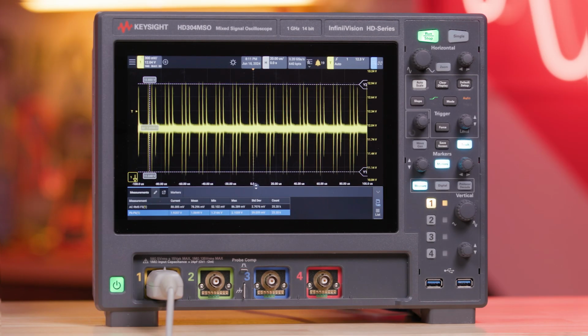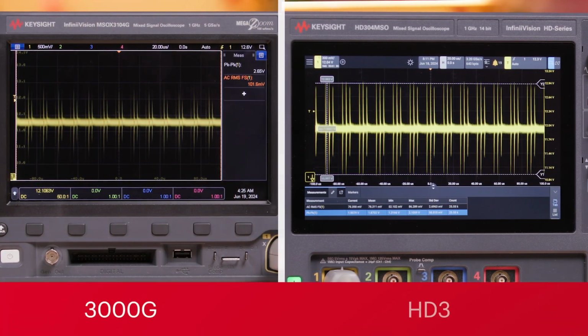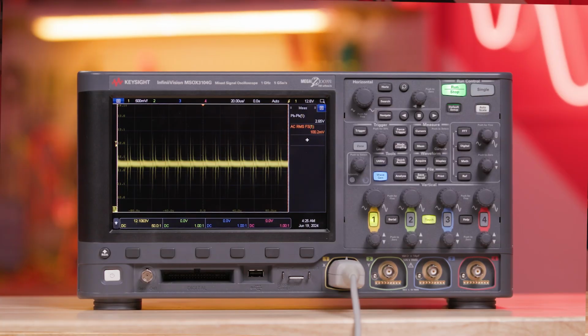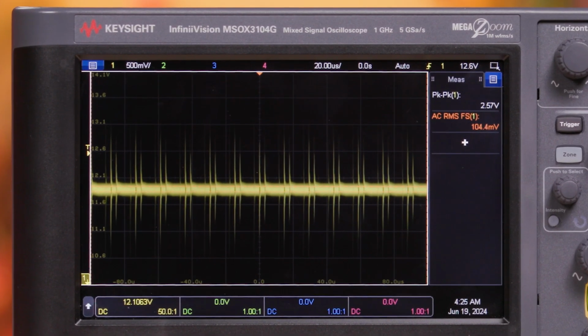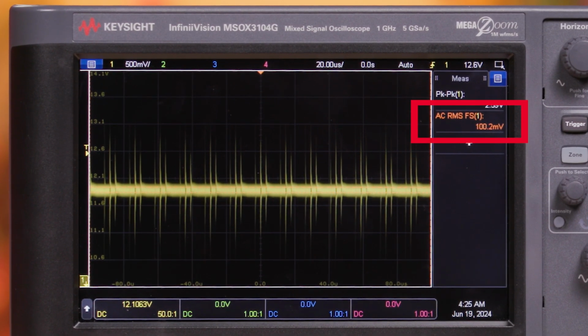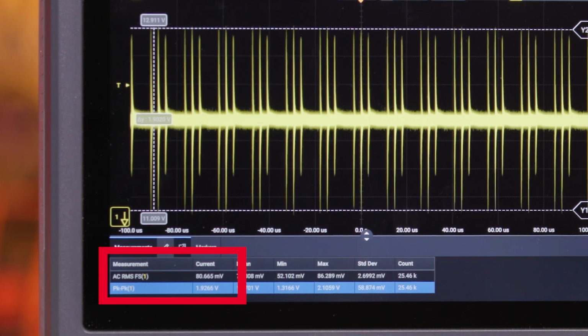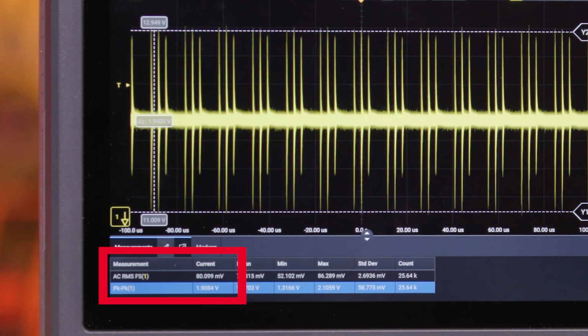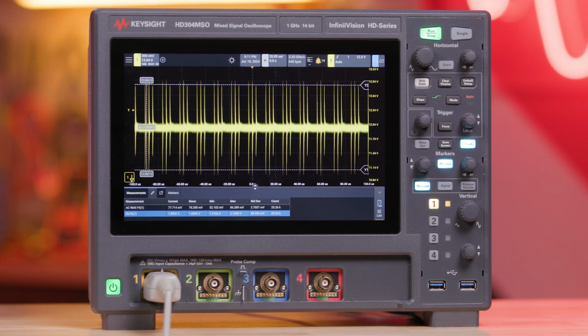Comparing these measurements on the HD3 to what I used to see on the 3000G, we can see what a huge difference this next level of vertical accuracy makes in these measurements. On the 3000G, with the same probe and scope settings, we are seeing a significantly higher RMS value than what we're seeing on the HD3. This difference in measurements is primarily driven by the front-end noise of the oscilloscope. With the lowest front-end noise, you won't see the HD3 interfering with any of these important measurements.